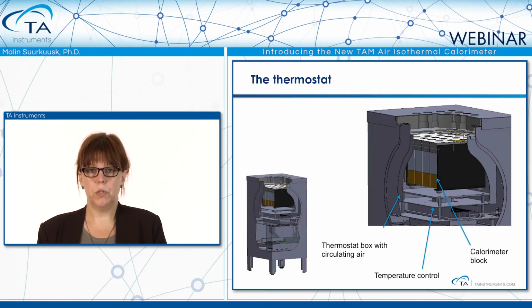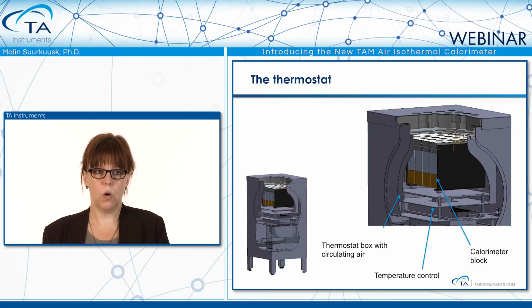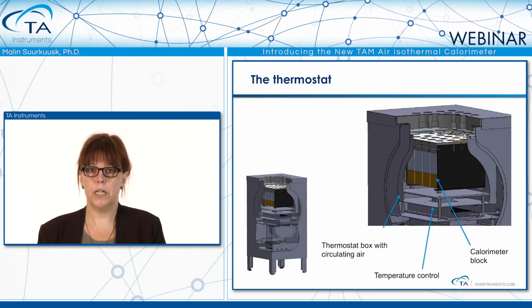And then this calorimeter block is put into the thermostat, which you see in the lower left corner is the whole thermostat cut away. In the bottom part of the thermostat is all the control electronics and communication cards to the computer. It's a floor model, so the height will be approximately that of a laboratory table. If we look at the right picture, we can see how the calorimeter block sits inside the thermostat box where the air is circulating. It's actually 2 boxes, so you have one box where the air comes in and flows on all sides of the calorimeter, and then it overflows and goes on the outside of that box down to the temperature control part of the thermostat. In this way, we are also able to shield from external disturbances.